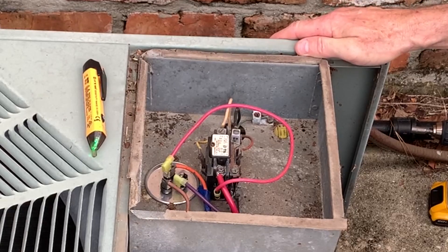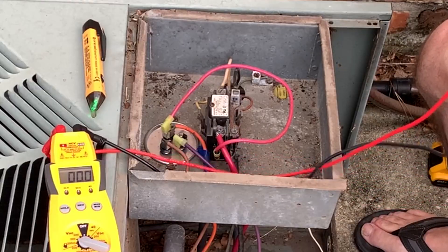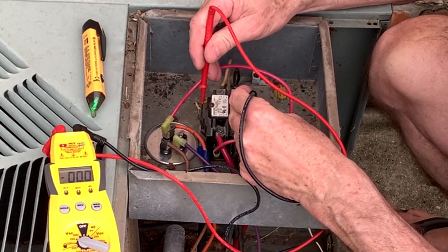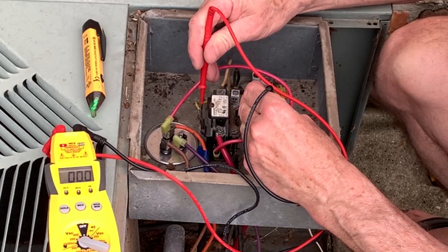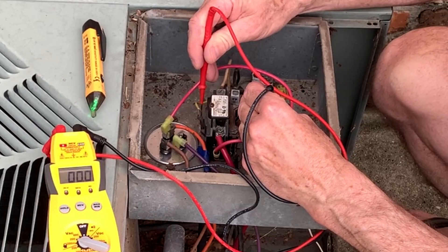I'll go turn the thermostat off and then we'll check the contactor. I just turned the thermostat off, and if you put the leads across the coil here, you can see I'm showing zero. So now the 24 volts is off.